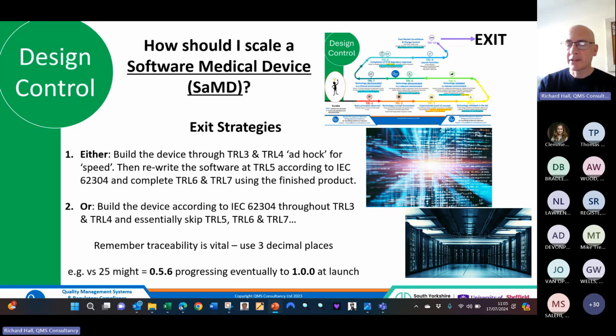In order for this all to make sense and to work for software, you need to make sure that you have version control. Version control is really important, and the best way of doing that is to have 3 decimal places. The third decimal place is used for bug fixes and keeping the software working. The middle decimal place will be things like usability engineering and usability factors. The first decimal place would be things like the intended use of the device.